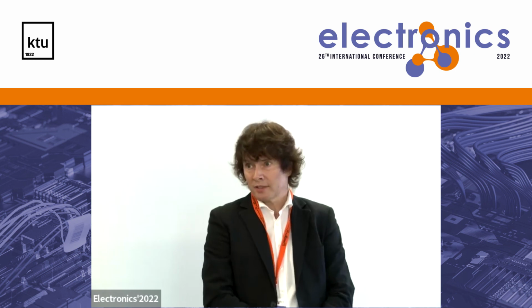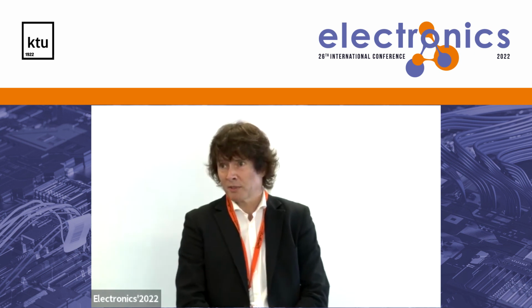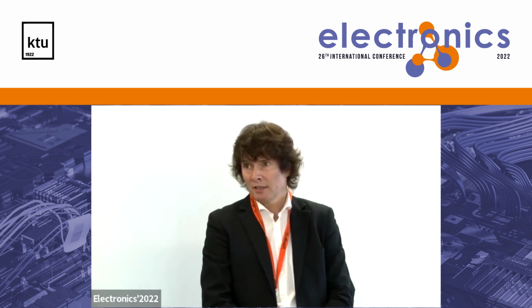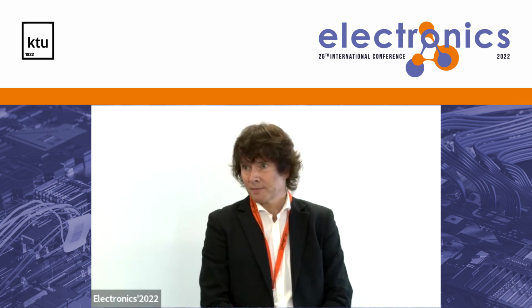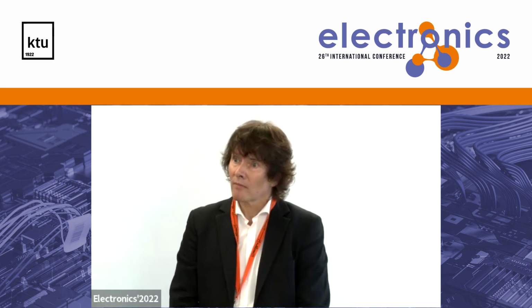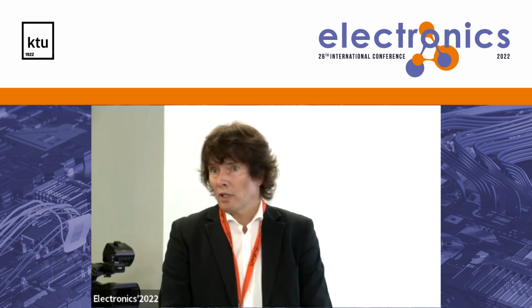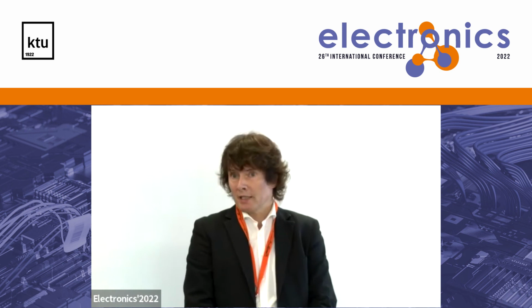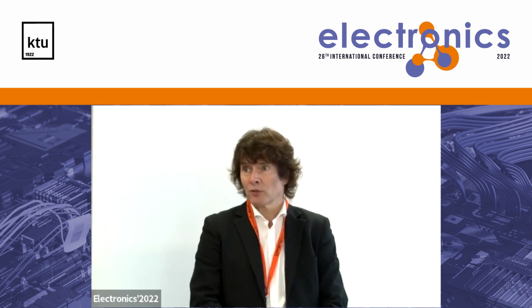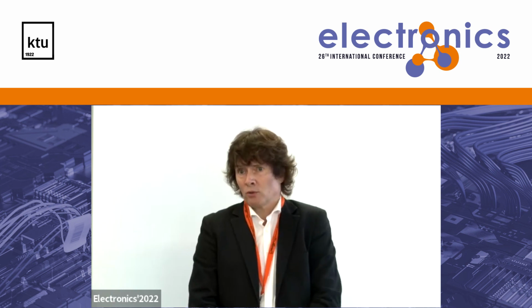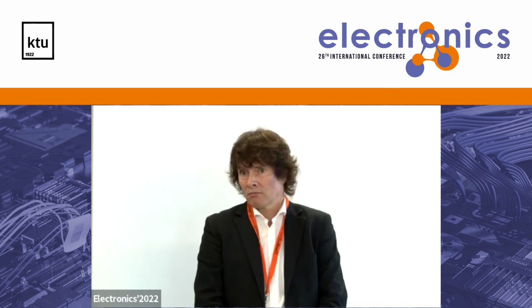Stabilizers, yes—the conventional power system stabilizer installed in the excitation system. Maybe for the whole power system it is really dangerous to have wide area oscillations, and maybe batteries could help damp wide area oscillations between countries. Yes, for other types of oscillations I believe batteries should be very successful. I think so, yes.